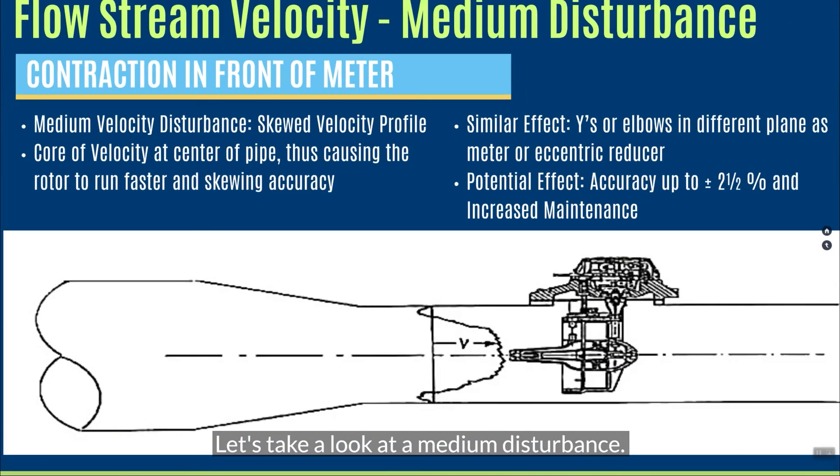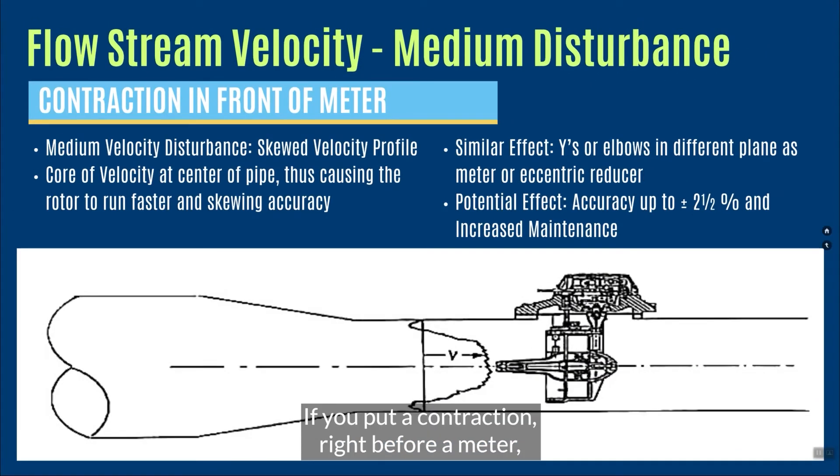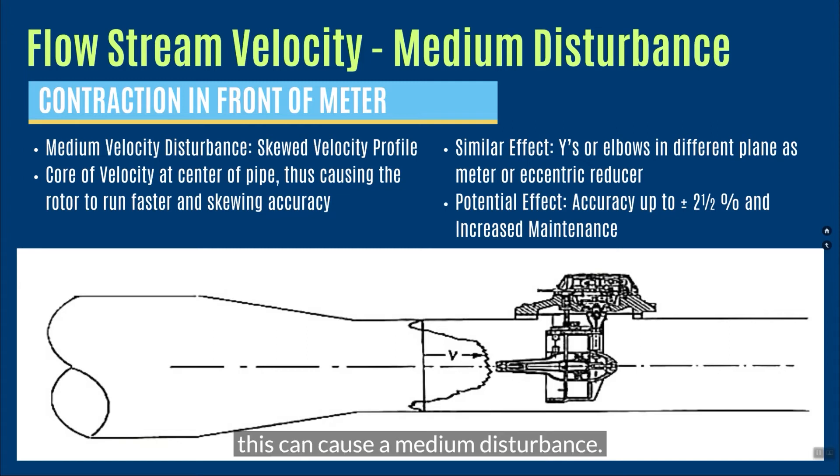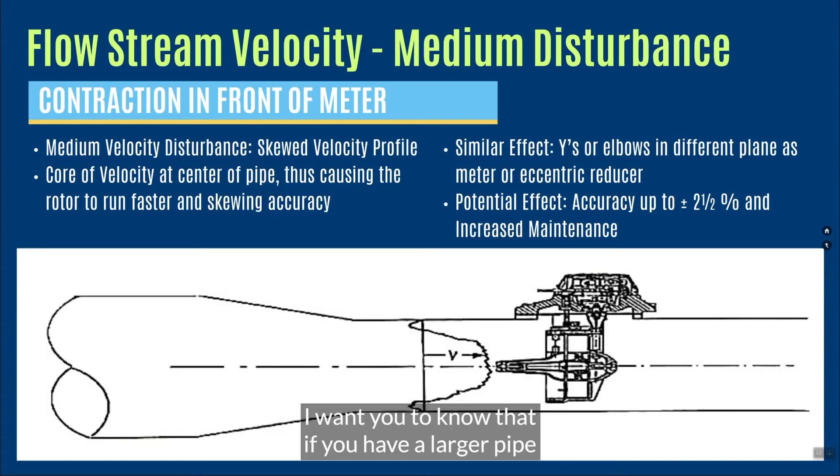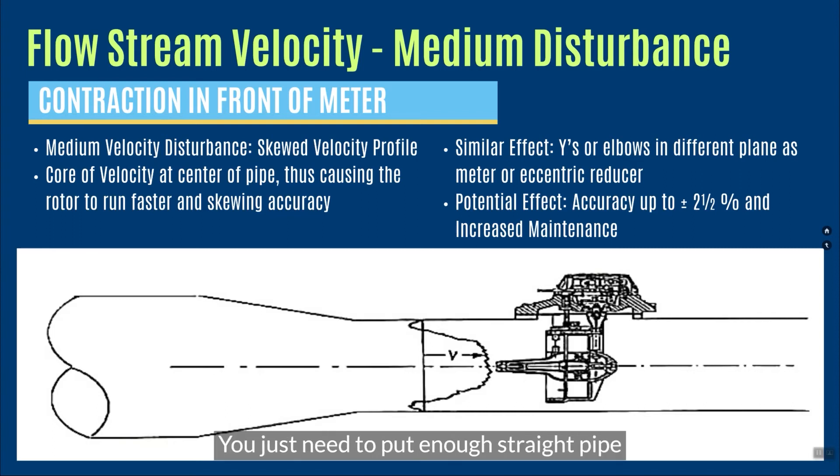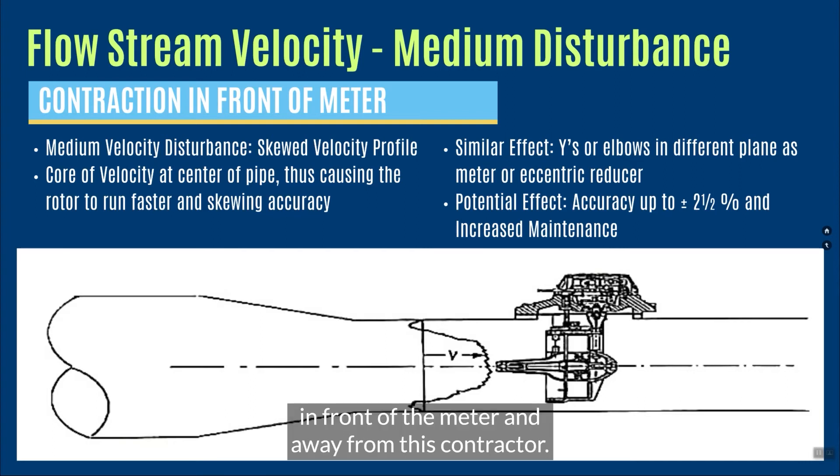Let's take a look at a medium disturbance. If you put a contraction right before a meter, this can cause a medium disturbance. I want you to know that if you have a larger pipe and you need to put in a smaller meter, you can do that. You're supposed to do that if it fits the application. It's okay to downsize a meter. You just need to put enough straight pipe in front of the meter and away from this contraction.